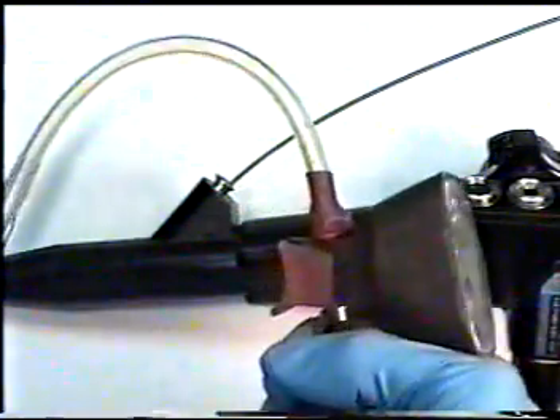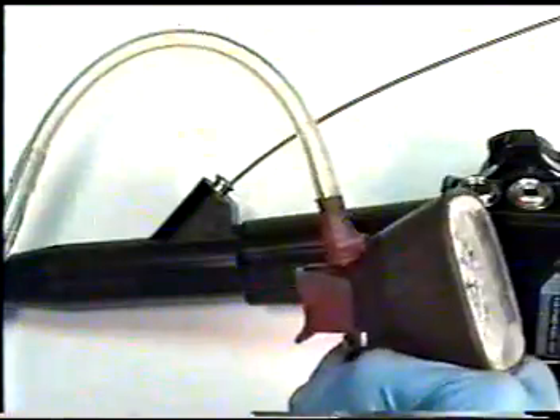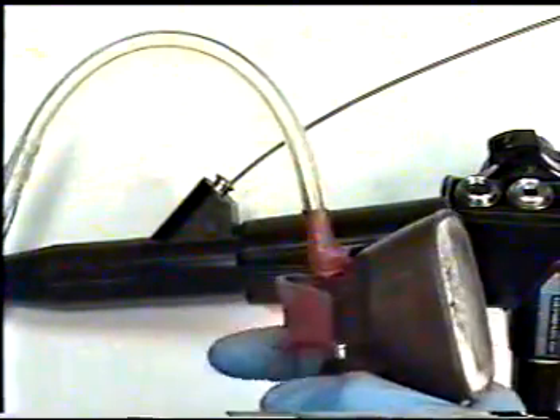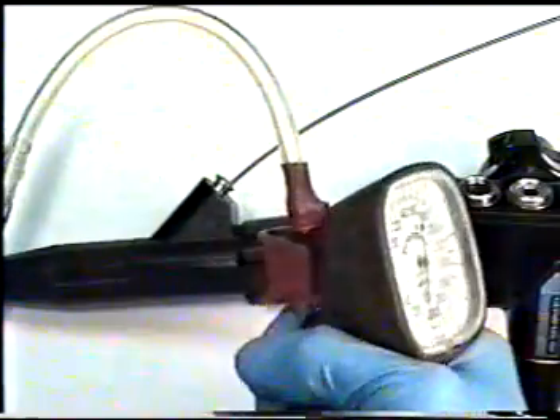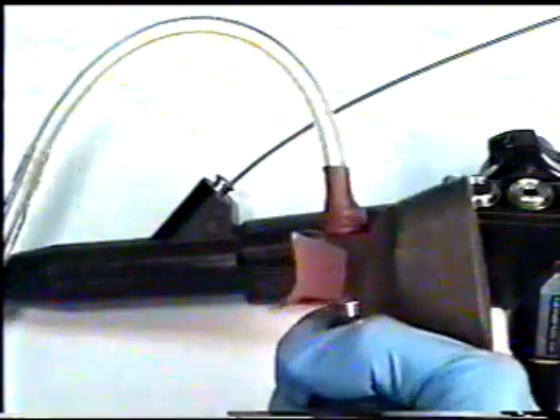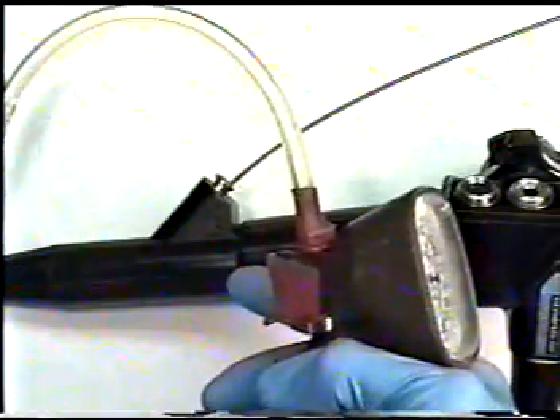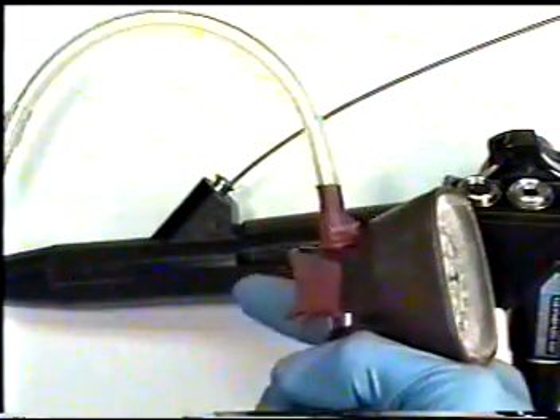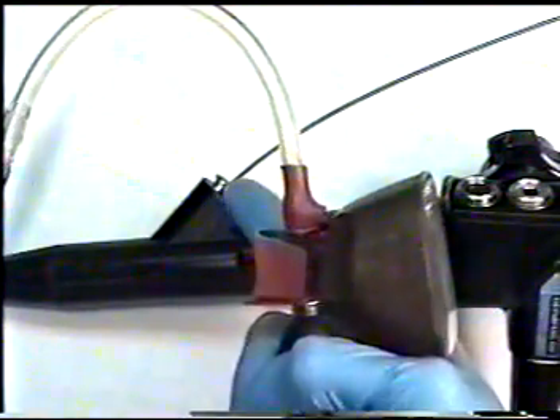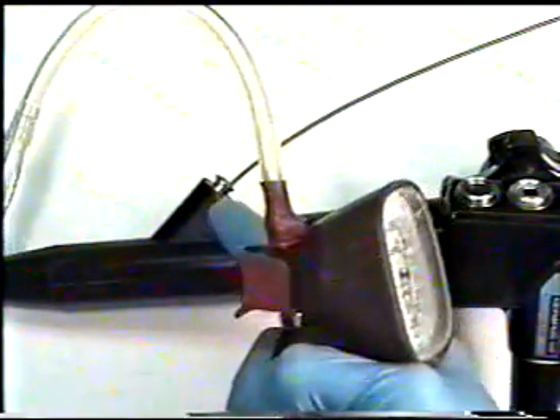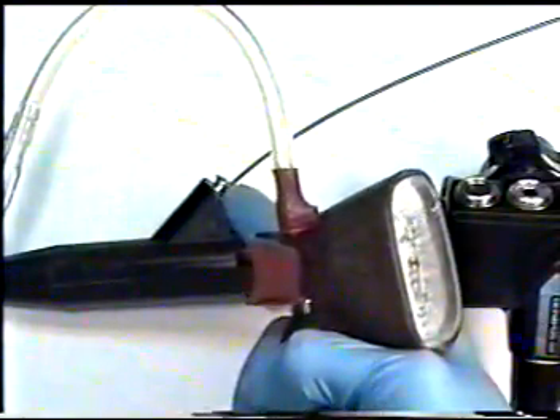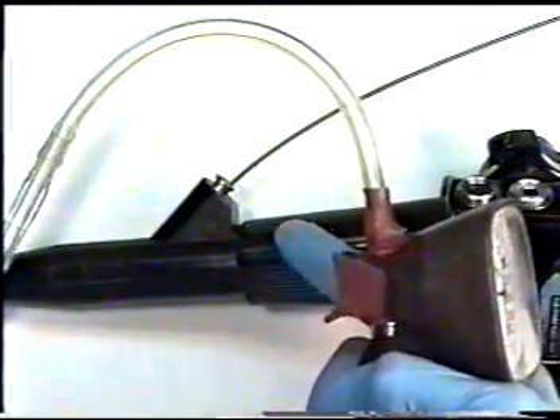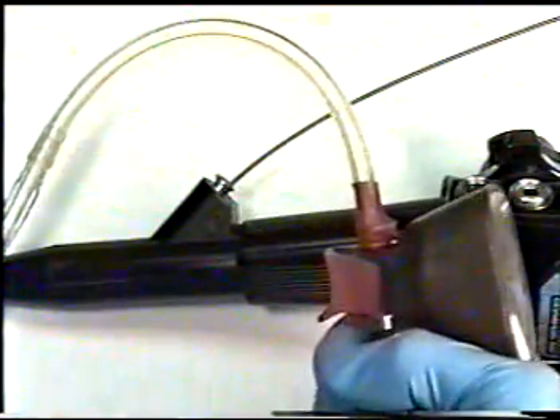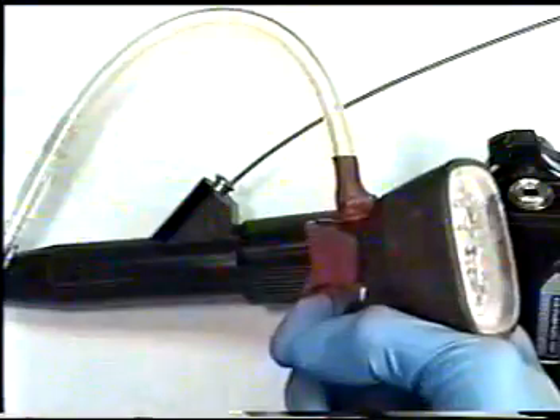And finally, be sure to pressurize your endoscope to make sure that all the body covers and distal end assembly and biopsy forceps channel tube opening and port are holding pressure. Submerge the instrument in a sink full of water and check for any leaks. If there are any leaks in the body control sections or your biopsy forceps channel itself, it may have been punctured during reassembly or during reinsertion onto the tip of the distal end, so be sure that there are no leaks of air out of your instrument before use and sterilization.